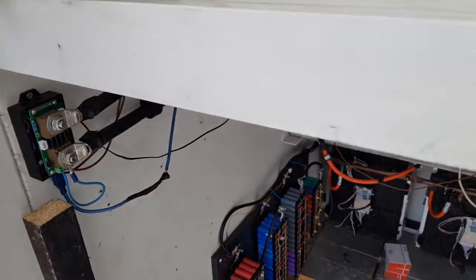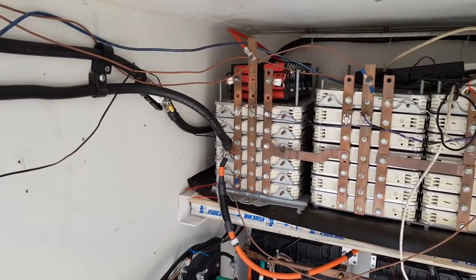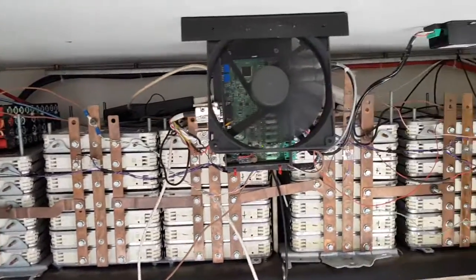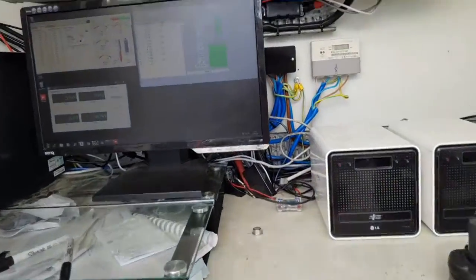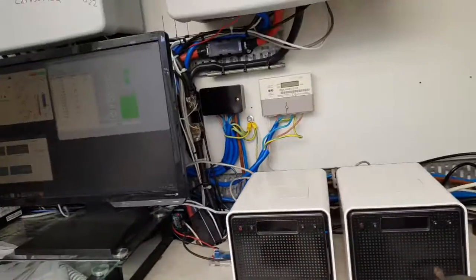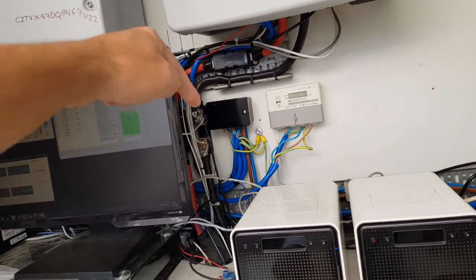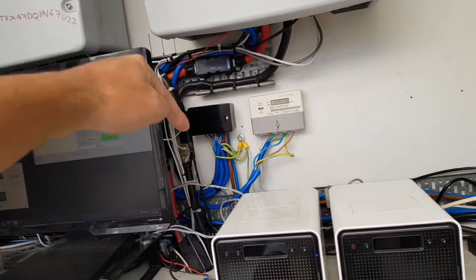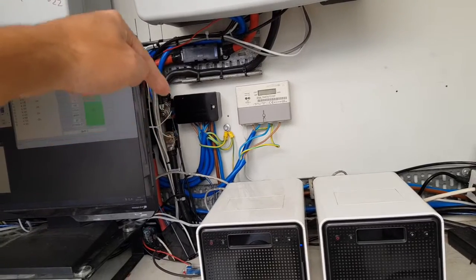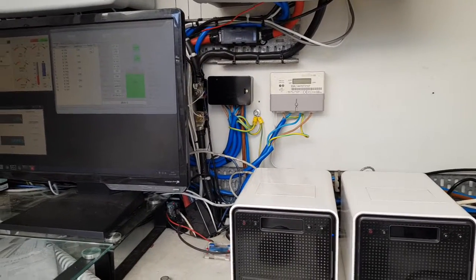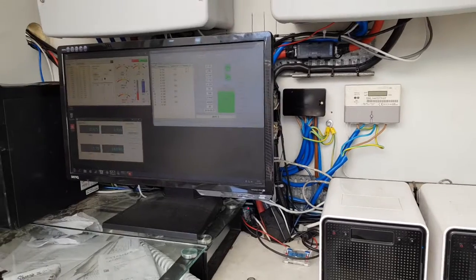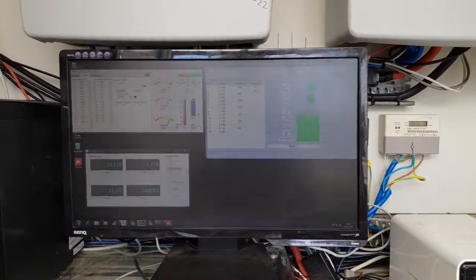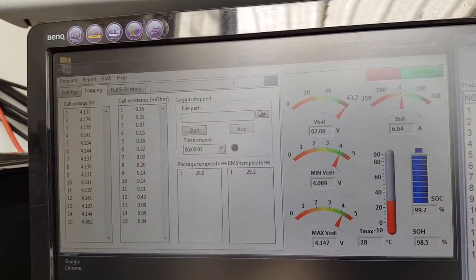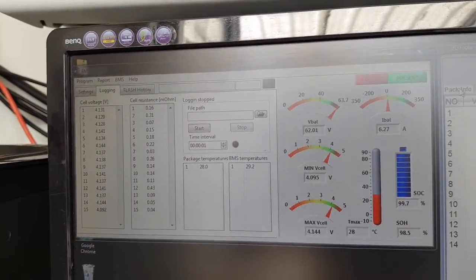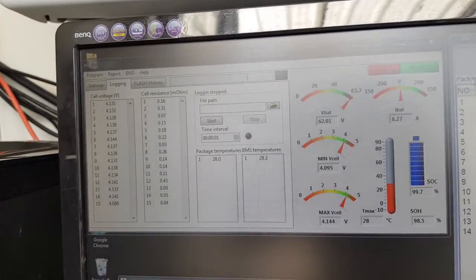And then that goes all the way back, through many fuses, comes out, and there's another shunt, which is connected to the main BMS. That's what's measured by the BMS that talks with the Sunny Islands, so the Sunny Island knows how much is going in, going out, how much it needs to charge, how much is charged already, and it works all of that out.